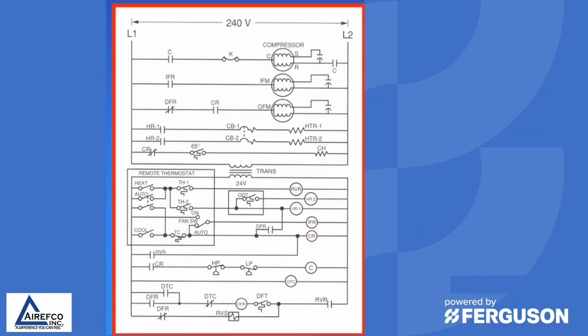By understanding how the symbols depict various switches, you can understand how the system operates. For example, the temperature switch closes on temperature drop. So anytime the temperature is above 65 degrees, this switch will be open. When the temperature drops below 65 degrees, the switch will close and remain closed until the temperature goes above 65 degrees. Whereas on the high pressure switch, this switch will be activated when the pressure rises, and so the switch will open when there is high pressure in the system. Conversely, the low pressure switch will close when the pressure rises and will open when the pressure gets low enough to open the switch.